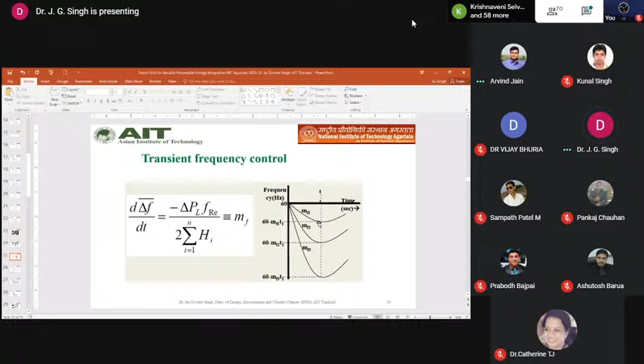Based upon that, the rate of change of frequency is the change in demand divided by inertia. And this graph shows that if you have a low H value, then this is the drop of frequency for the same change in load. Please keep in mind, for the same change in load, you have a high drop in that period. If you have high inertia, then the drop is low. So this will affect the grid operation. You know that you can't allow frequency to drop below a certain value.